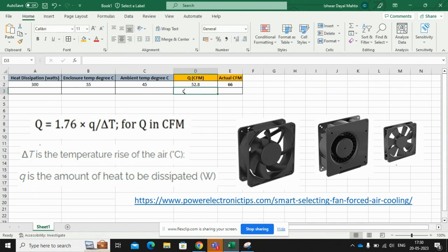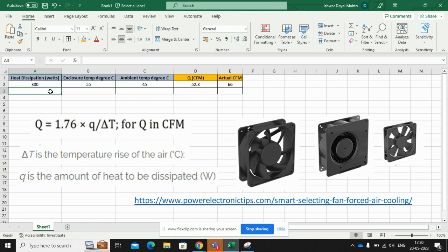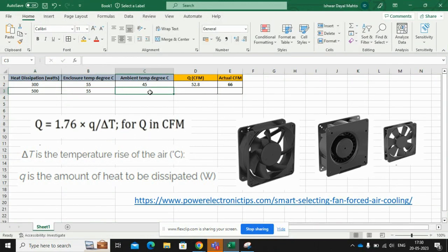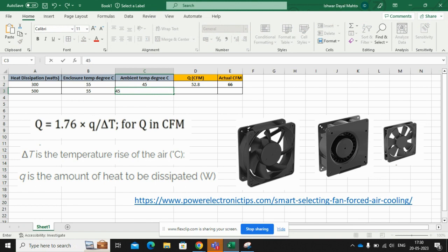Now I'll take one more example to show how to calculate the CFM. Let us take heat dissipation 500 watts, enclosure temperature 55, and ambient 45 degrees. These are the worst case temperatures I have taken.